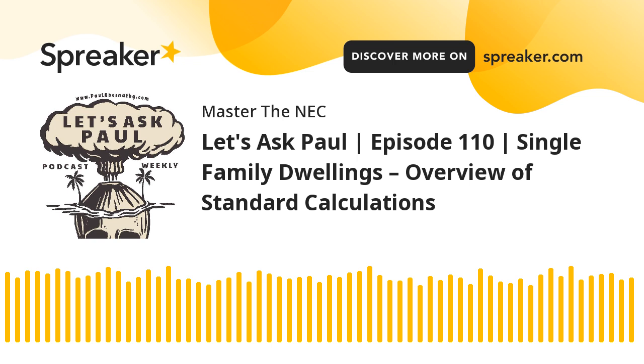Full value. But if we have 4 or more appliances, like maybe a garbage disposer, dishwasher, trash compactor, and maybe we have an attic fan or something like that, that would qualify as an appliance, then if we have 4 or more, we're going to get a 75% reduction, okay? But we get to apply 75%, I should say that. It's basically a 25% reduction, but we get to apply the 75% to that, okay? All right, so we do so, and that's pretty straightforward. We just take whatever the number is, and I also should remind you that a water heater, for example, is a fastened in place appliance, usually 4,500 watts, okay? So we're just going to take that, and dishwasher, disposer. If we've got 4 or more, then we add them all up and then just multiply it by 75%.